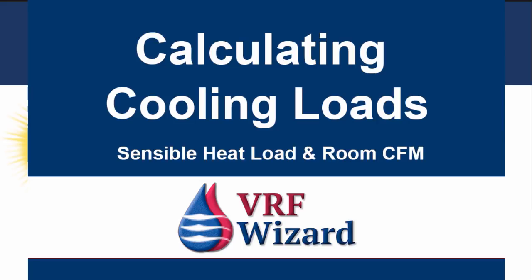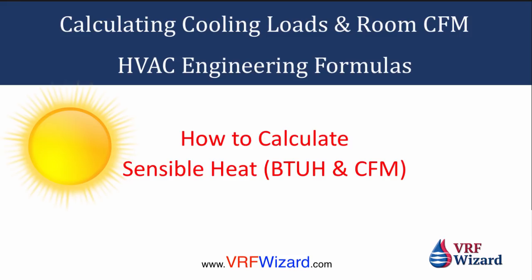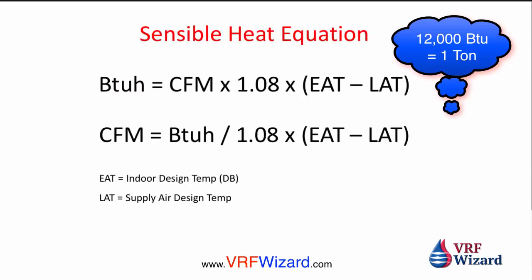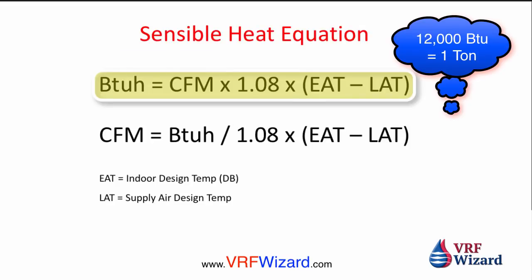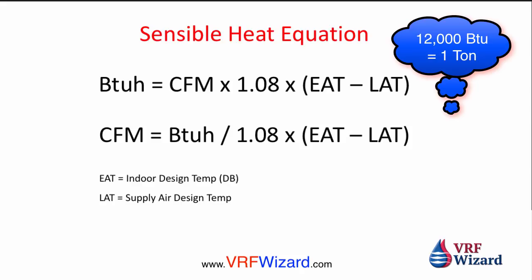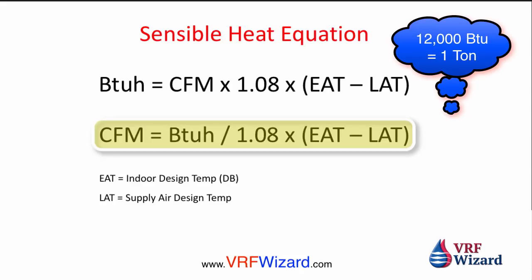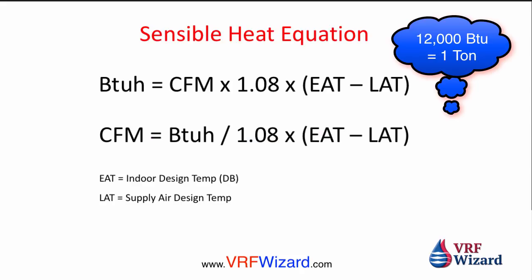We're going to cover how to calculate cooling loads, and then once you have your cooling load you can figure out how much CFM is required. This is based on sensible heat — these are your sensible heat equations. We're going to figure out BTUs per hour first, and from there we can determine how much CFM we're going to need for the room. Our indoor design temperature — the entering air temperature — is 75°F, and our supply air design temperature is 55°F.